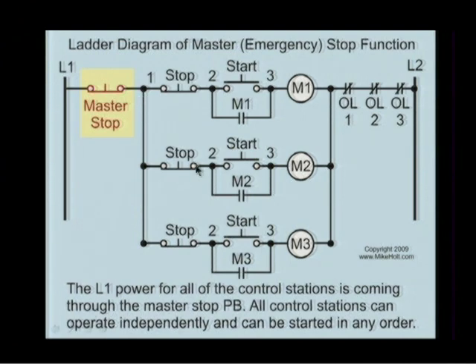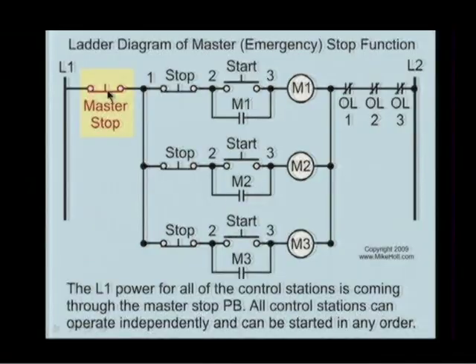Well, if you want everything to come off, then you want to make sure. Here's an example where you'd want to have a separate circuit for your control circuits, right? Not tap off of each motor branch circuit. You want to make sure you have a 20 amp breaker at the panel, and you come over, and now you can supply all the different controls that you want to be able to turn off, and put a master stop button right there, and you just run over there with maybe a mushroom head, boom.